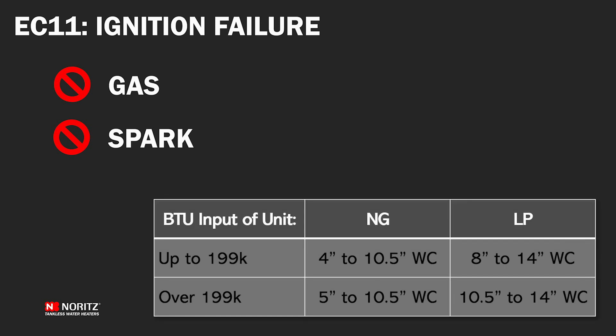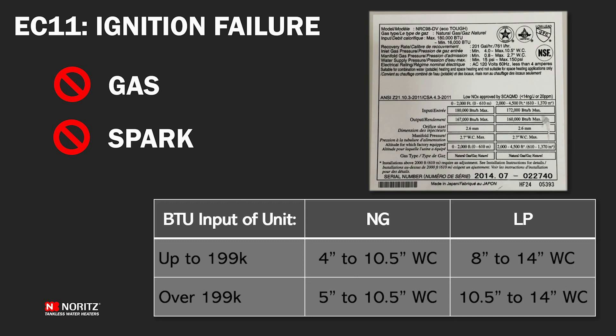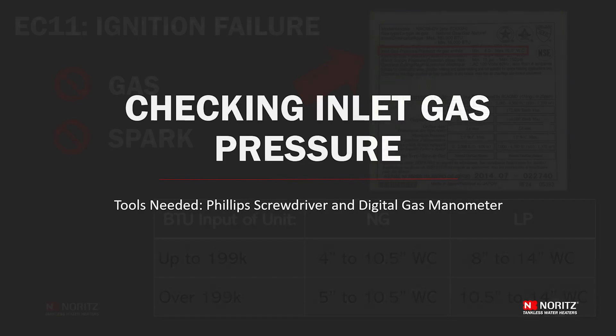Here are the minimum and maximum inlet gas pressures required based on the max BTU input and gas type of the unit. You don't need to memorize this chart as the required minimum and maximum gas pressures are listed right on the rating plate of the unit. I will show you two troubleshooting steps that account for the majority of error code 11 causes: checking the inlet gas pressure and cleaning the ignition rod assembly.